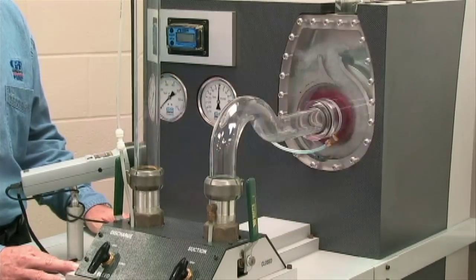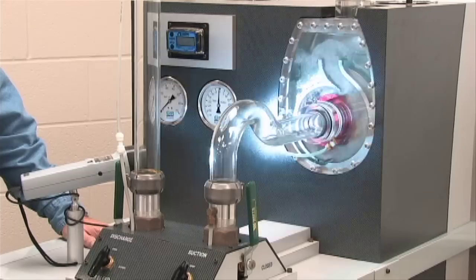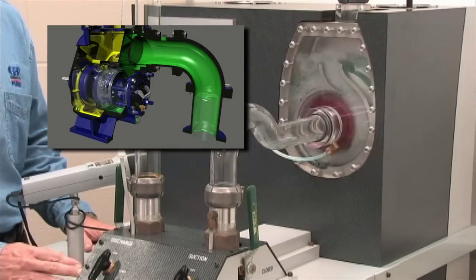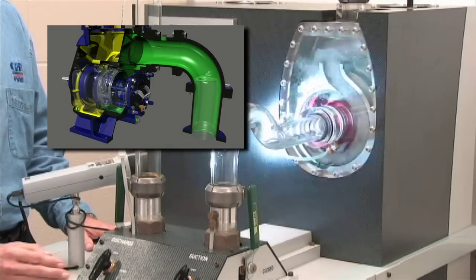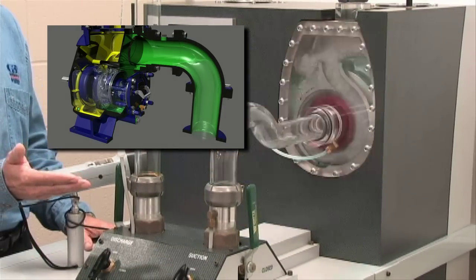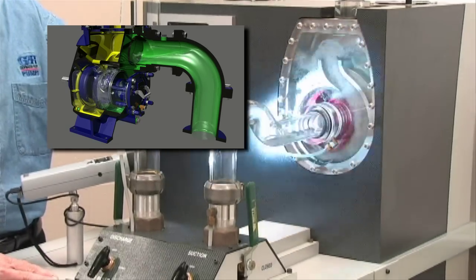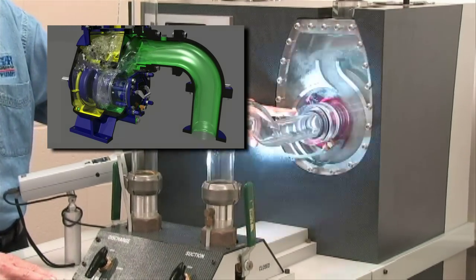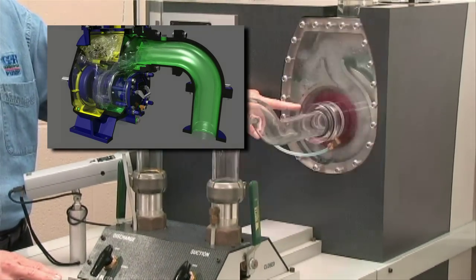Due to that differential in pressure, atmospheric pressure outside begins to force liquid up the suction pipe. As liquid moves up the suction pipe, it pushes all the air ahead of it into the volute casing where it is handled through the recirculation process.